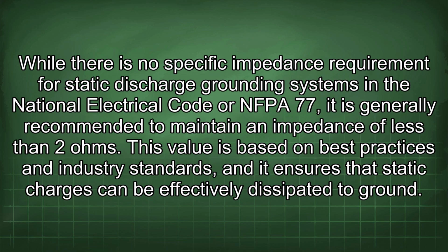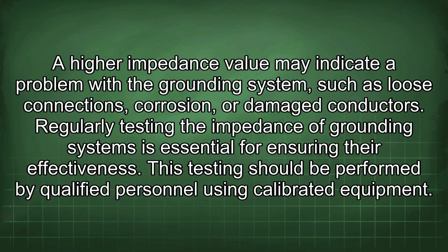While there is no specific impedance requirement for static discharge grounding systems in the National Electrical Code or NFPA 77, it is generally recommended to maintain an impedance of less than 2 ohms. This value is based on best practices and industry standards, and it ensures that static charges can be effectively dissipated to ground. A higher impedance value may indicate a problem with the grounding system, such as loose connections, corrosion, or damaged conductors. Regularly testing the impedance of grounding systems is essential for ensuring their effectiveness.